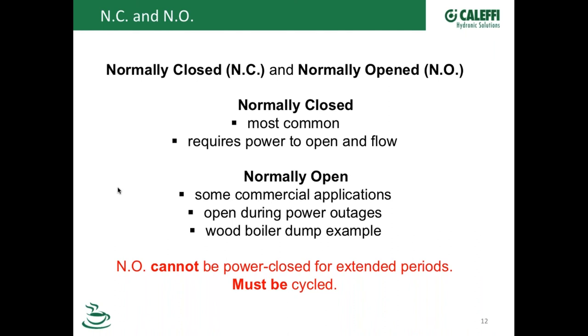It does cause some issues with the lubrication inside there, but not only that, to power them closed for say 3 or 4 months out of the summer, you're just wasting energy, and so you need to cycle those valves every now and then, or have some type of a design within your controls to allow those to unpower during summer months, maybe with warm weather shutdown or something like that. Yeah, it's a good point to exercise them basically.